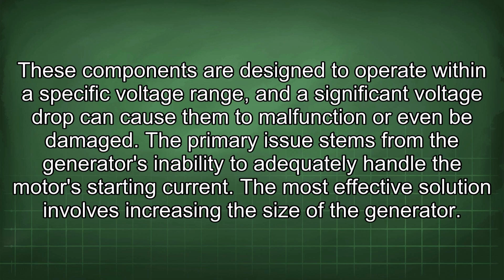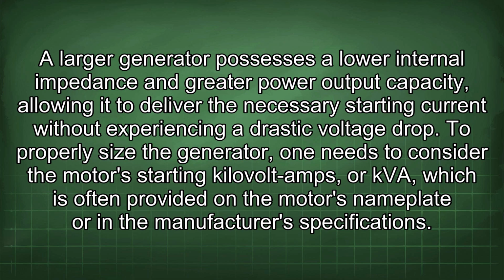The primary issue stems from the generator's inability to adequately handle the motor's starting current. The most effective solution involves increasing the size of the generator. A larger generator possesses a lower internal impedance and greater power output capacity, allowing it to deliver the necessary starting current without experiencing a drastic voltage drop. To properly size the generator, one needs to consider the motor's starting kilovolt amps, or kVA, which is often provided on the motor's nameplate or in the manufacturer's specifications.